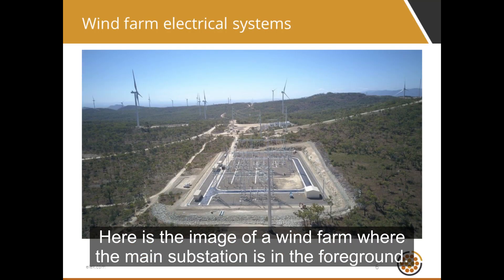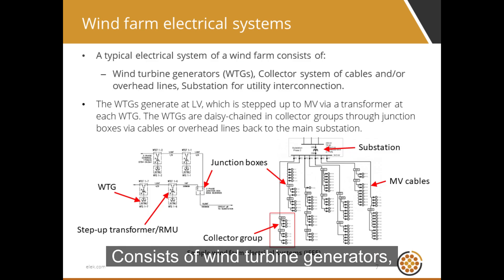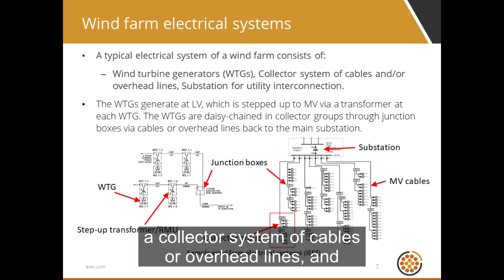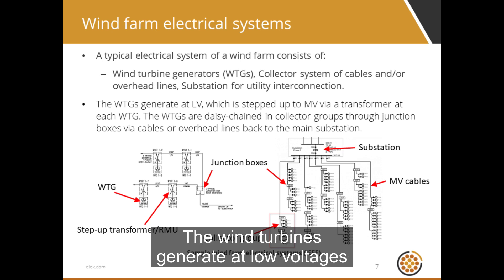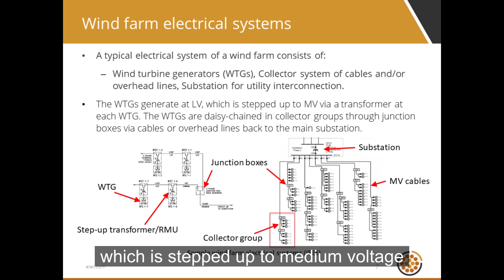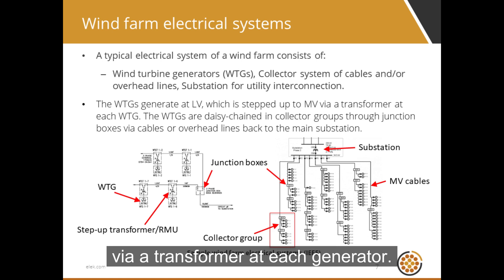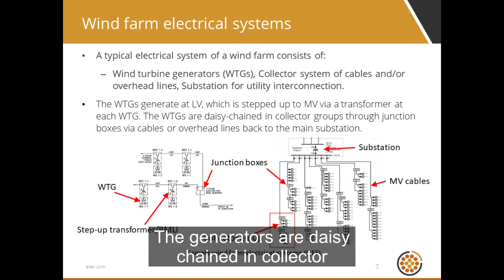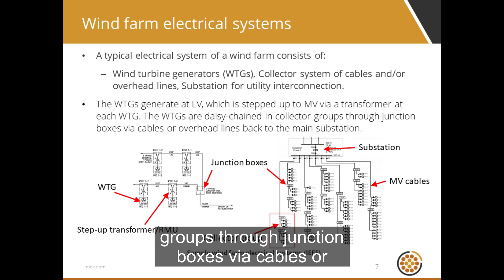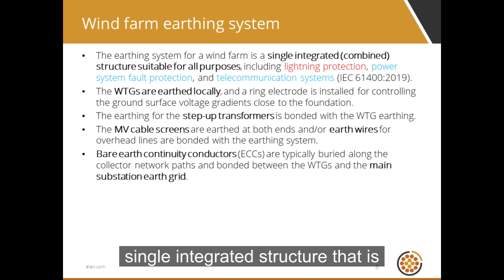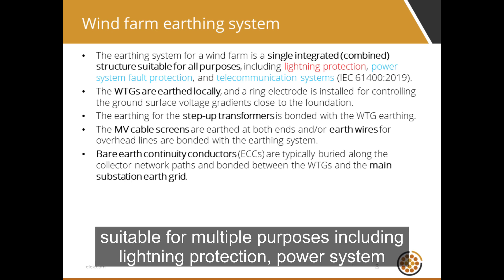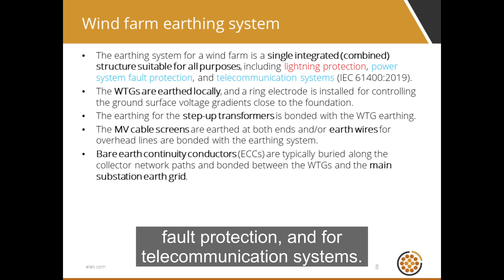We will start with discussing how to perform the earthing design and modeling for a wind farm. Here is an image of a wind farm where the main substation is in the foreground. The electrical system of a wind farm consists of wind turbine generators, a collector system of cables or overhead lines, and a substation for utility interconnection. The wind turbines generate at low voltages, stepped up to medium voltage via a transformer at each generator. The generators are daisy-chained in collector groups through junction boxes via cables or overhead lines to the main substation. The wind farm electrical system is a single integrated structure suitable for lightning protection, power system fault protection, and telecommunication systems.